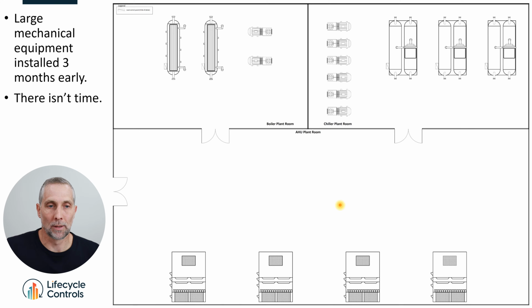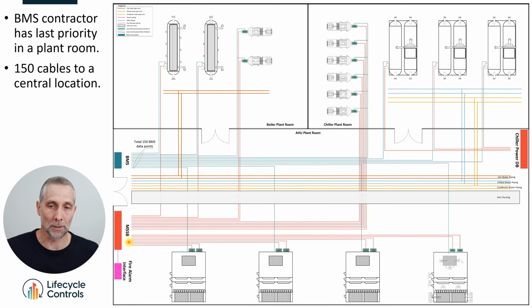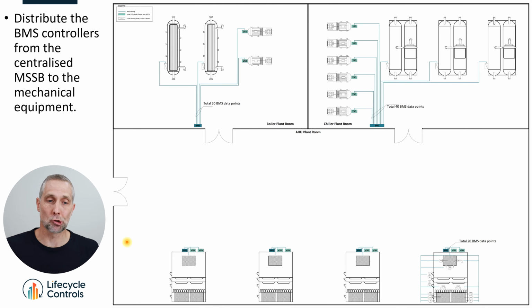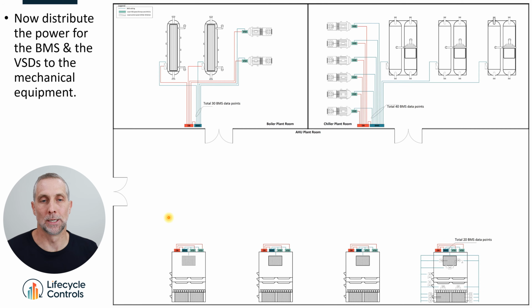We've got to try and do something differently. And the first idea here is that this mechanical control panel is a massive bottleneck in the BMS. And if we can get rid of this mechanical control panel, it's going to speed things up really quickly for us. So the first thing we're going to do is distribute the controls. Before, we had this centralized control panel with 10 or 20 BMS controllers in there. We're distributing all the controllers out to where the equipment is. So in the boiler plant room, we've got a BMS panel with those controllers in. In the chiller plant room, we have a BMS panel with those controllers in. And on every single air handling unit, we have a very small panel with just one controller in, and we're distributing the controls across. I've also shown here that the variable speed drives are being installed at the same time. And then we distribute the power.